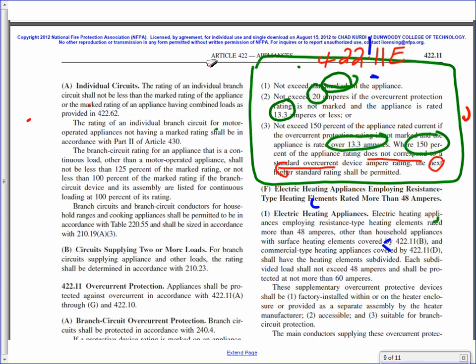If you read through this, this is for non-motor appliances, an appliance that does not have a motor in it. Does the water heater have a motor? No, it doesn't have a motor. So here's what the NEC code book says about appliances. It says not to exceed the nameplate rating, and the first one, not to exceed 20 amps if the overcurrent protection rating is not marked and the appliance is 13.3 amps or less. So if you have an appliance that says 13.3 amps, you cannot exceed 20 amps. You put a 20 amp circuit.